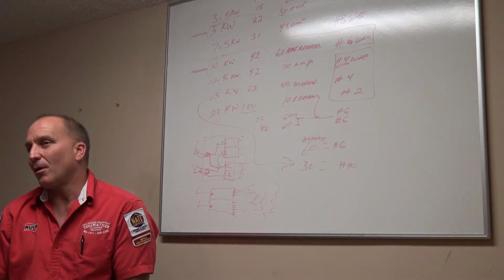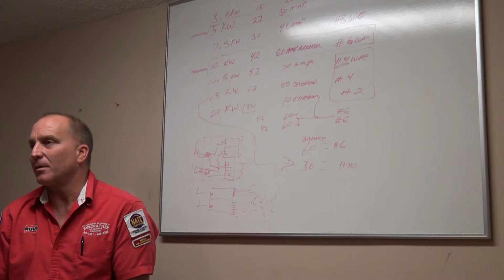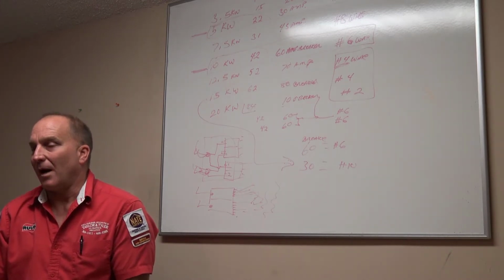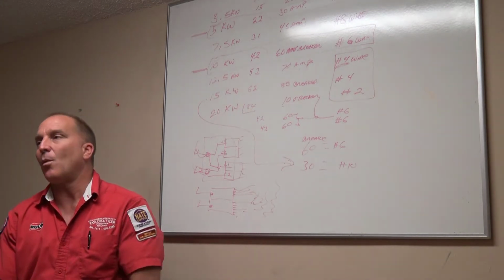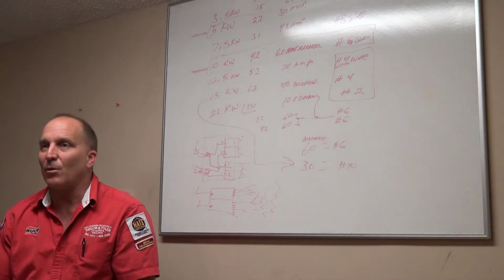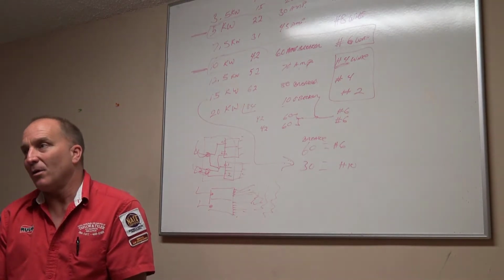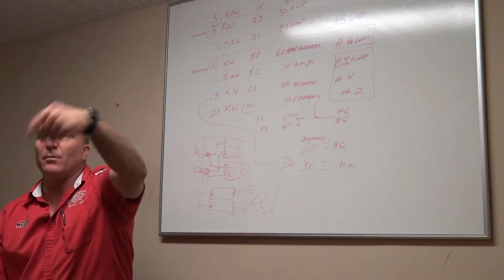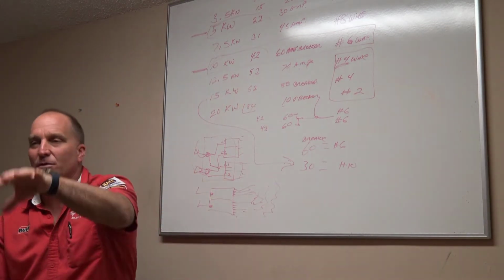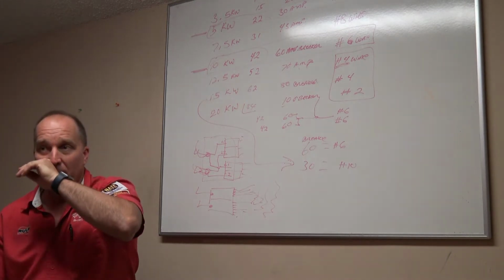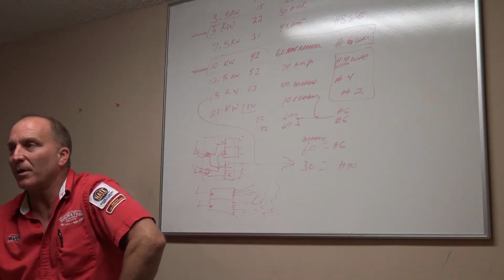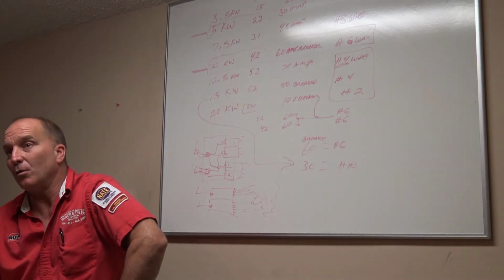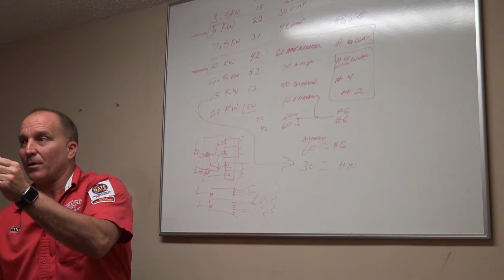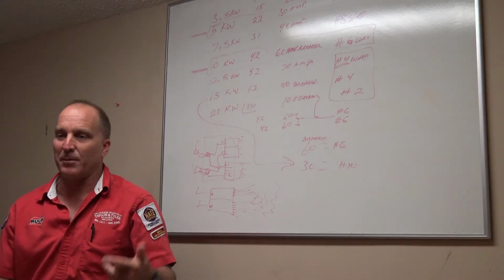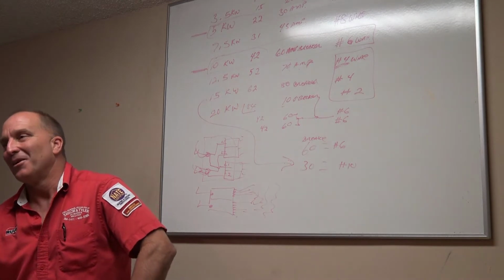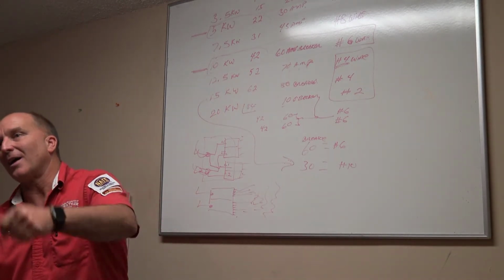Okay? You just start learning where all the wires are, because how many circuit boards have I replaced in my career? I used to mark every wire. I'd take a picture of it or whatever, and I'd mark every wire, and I wasn't sure where it went. Then after you do it 80 to 100 times, you're going, let me just pull all these damn wires off here. Get them off, get the circuit board out of the way, put a new circuit board in, and then you go, okay, this wire's going here, this wire's going there. Because when you've got 4 black wires, are they going to the correct place every time? Because you can literally move your IDM motor and plug your black fan motor into your IDM motor, and you turn your furnace on, and what happens? Your blower motor comes on. Well, a lot of times your spades on those are different sizes too, so you don't screw them up as well.